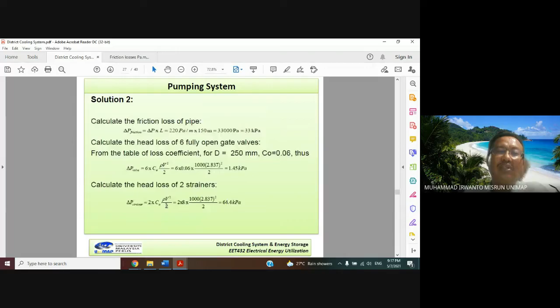And then the exchanger. The height from the question is 7, so height multiplied by rho multiplied by g. So 7 multiplied by 1000 for the density of the water, and gravity 9.81, is equal to 68.7 kPa. Okay, last for the friction is the cooling tower. The cooling tower has a head of 8 and 4, 4 meter for the open section. So the cooling tower friction loss is equal to H rho g, which is 4 times 1000 times 9.81, equal to 39.2 kPa.